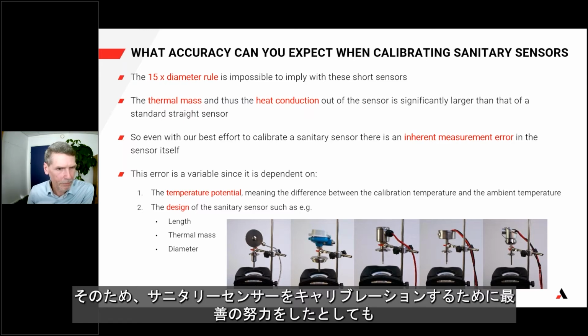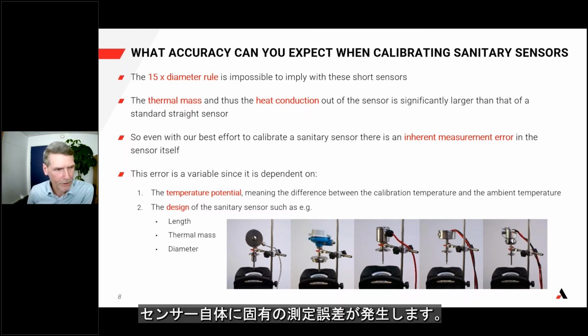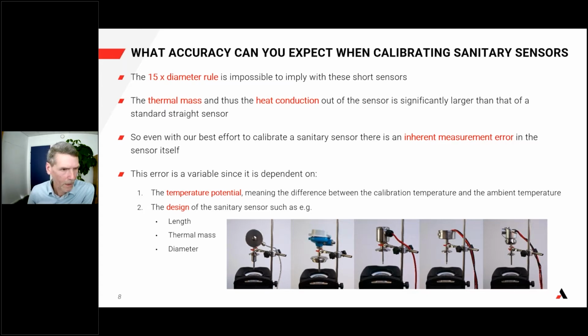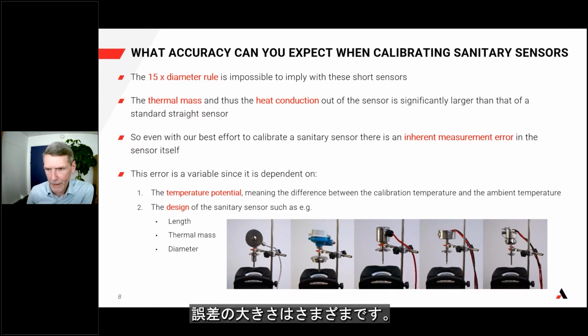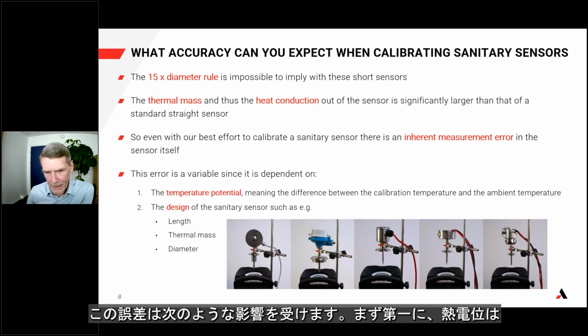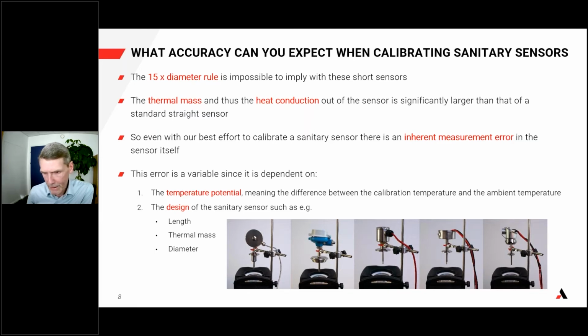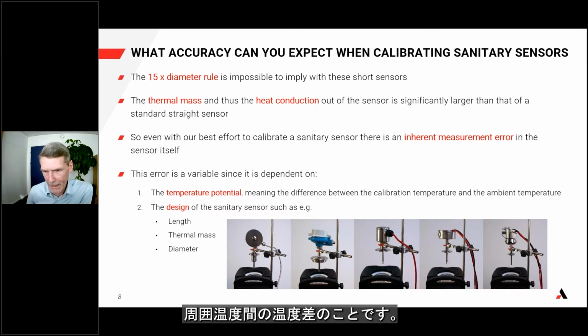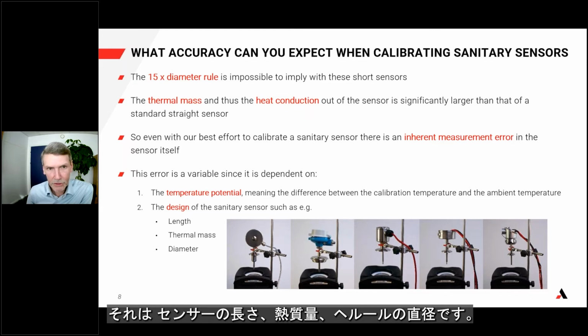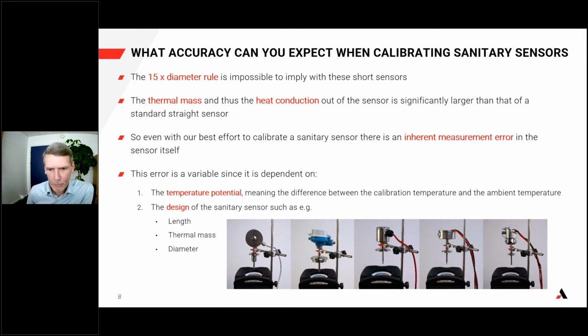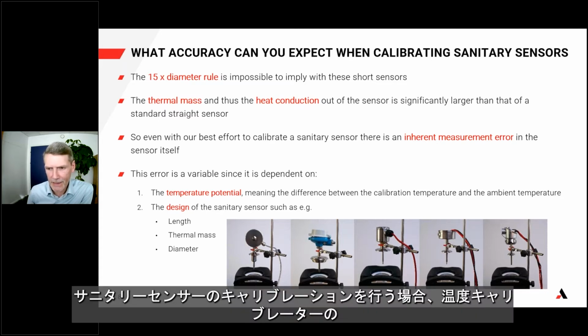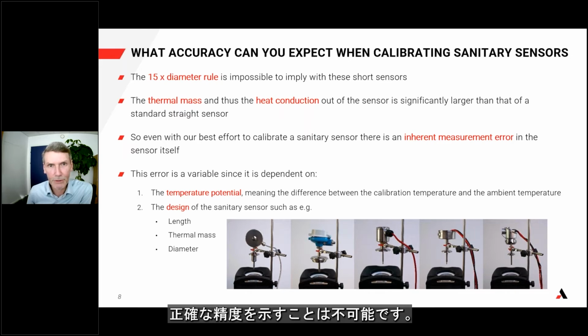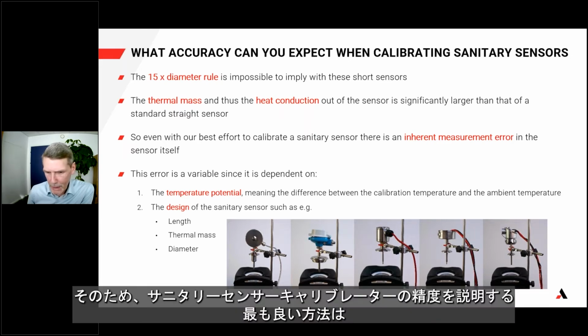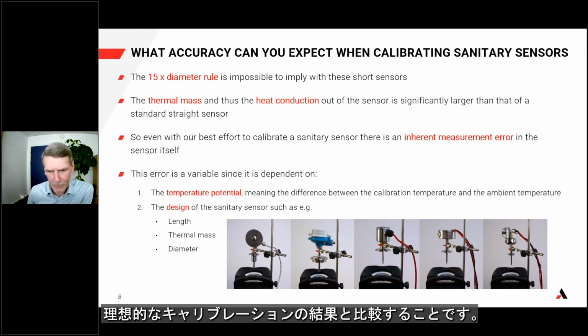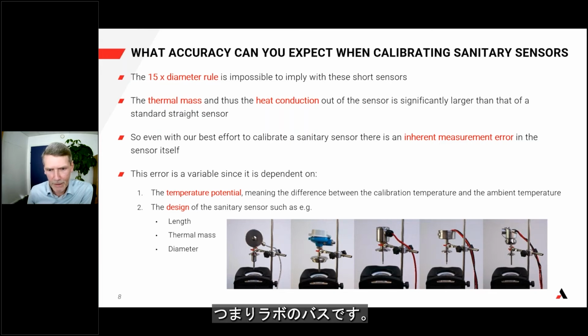So even with our best effort to calibrate a sanitary sensor, there is an inherent measurement error in the sensor itself. Different sanitary sensor designs will therefore cause errors of different magnitude. The error is impacted first of all by the thermal potential, meaning the difference in temperature between the measured and the ambient temperature. Then also the mechanical design of the sensor, that is sensor length, thermal mass, and clamp diameter. With that said, it is impossible to state an exact accuracy of a temperature calibrator when calibrating sanitary sensors. So the best way to describe the accuracy of a sanitary sensor calibrator is to compare the result with that of an ideal calibration, namely in a laboratory bath.